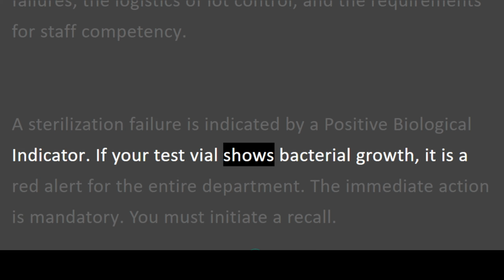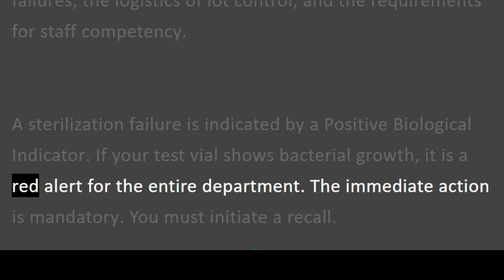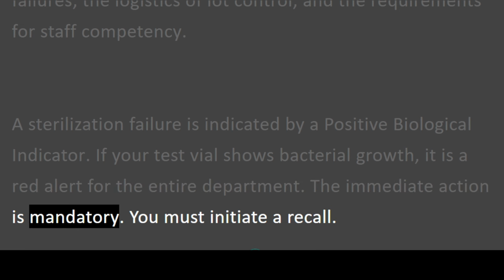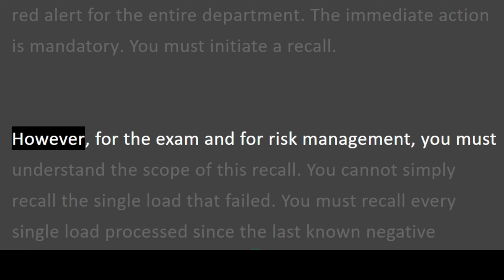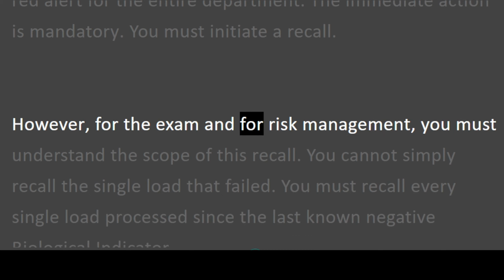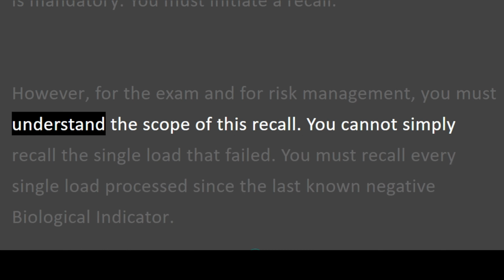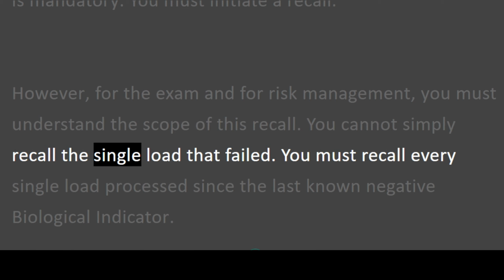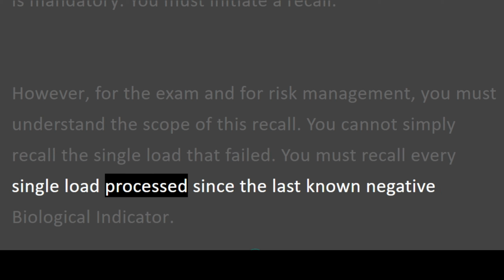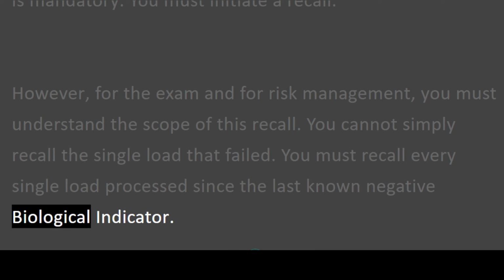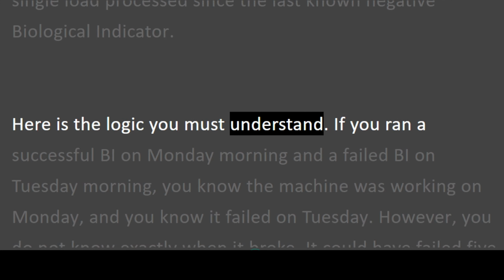If your test vial shows bacterial growth, it is a red alert for the entire department. The immediate action is mandatory. You must initiate a recall. However, for the exam and for risk management, you must understand the scope of this recall. You cannot simply recall the single load that failed. You must recall every single load processed since the last known negative biological indicator. Here is the logic you must understand.